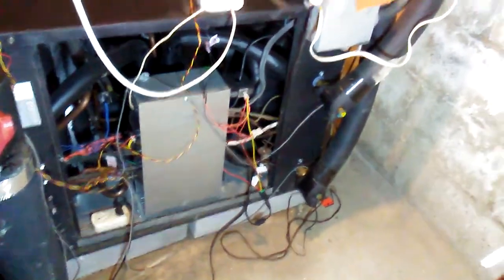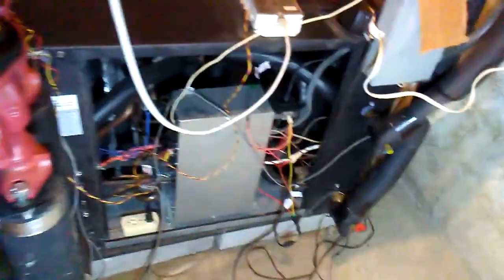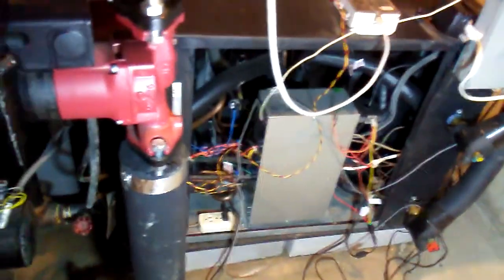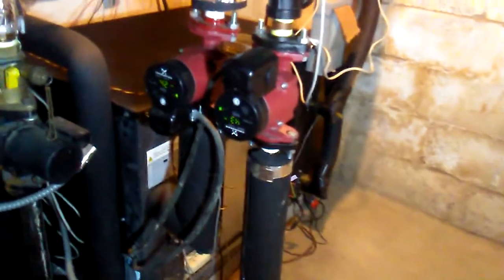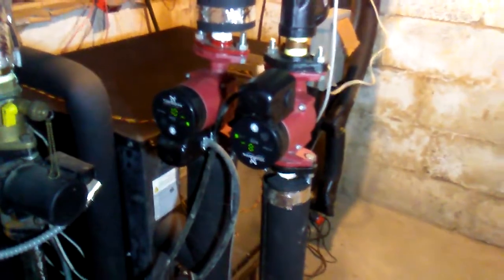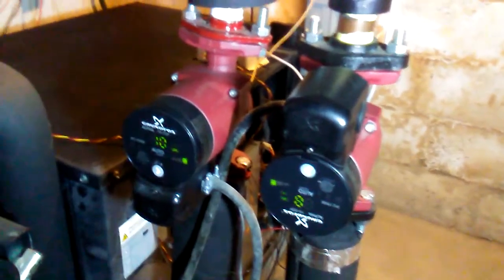Goes back up and out through this pipe and back out to the loops. Over here is the load side of the heat pump, and we have here the two ECM circulators. You can see they're running at 42 watts and about 10 gallons a minute.